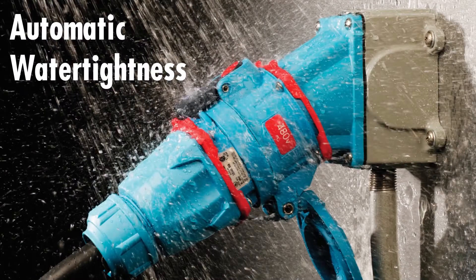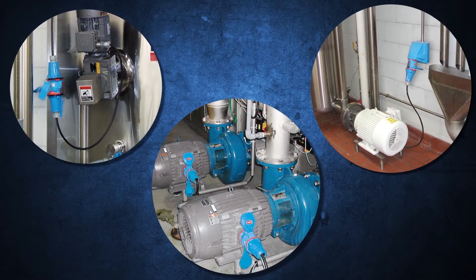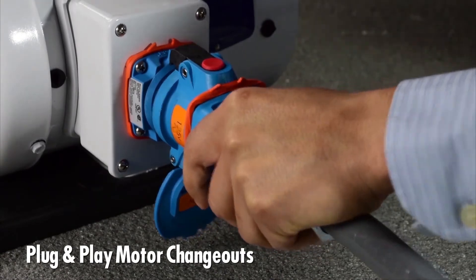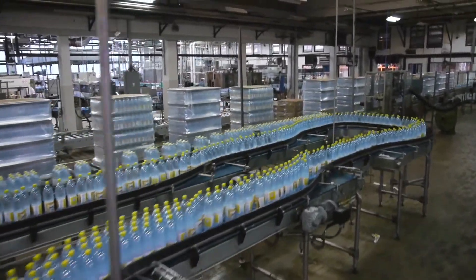Rated water tightness up to Type 4X is achieved automatically when the plug is mated to the receptacle. When Meltric switch-rated plugs and receptacles are installed, downtime-critical motors can be replaced with plug-and-play simplicity, so conveyor lines or process pumps can be up and running in a matter of minutes instead of hours.